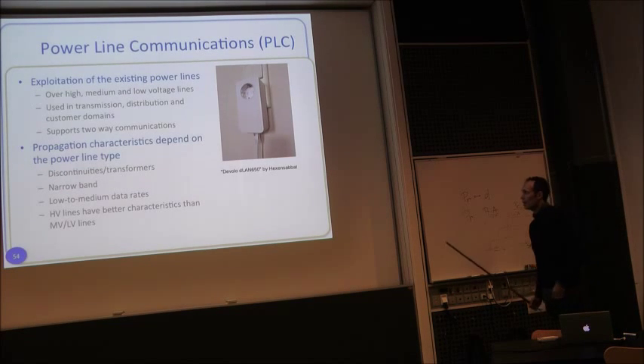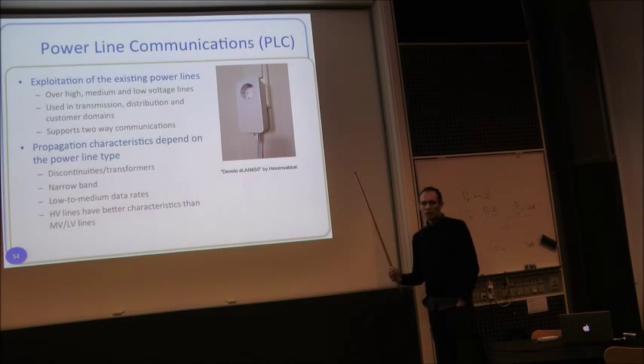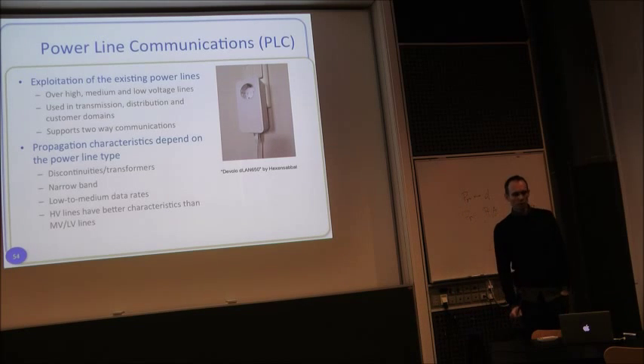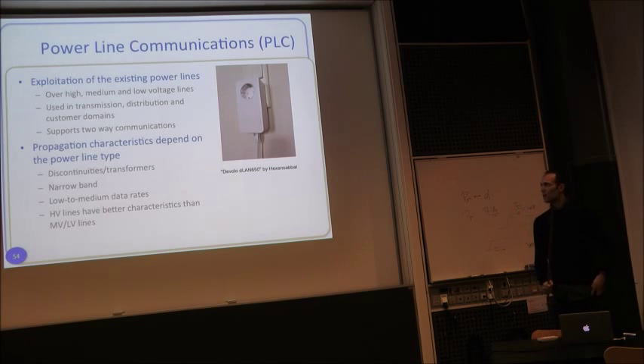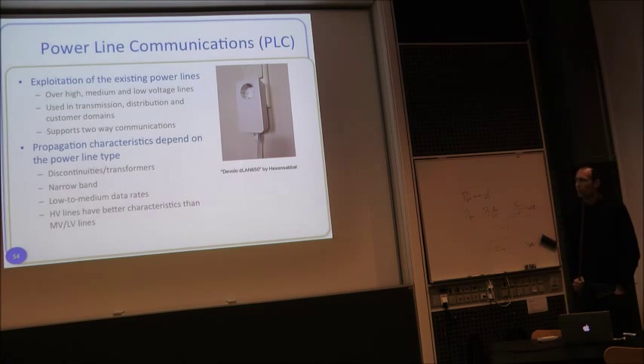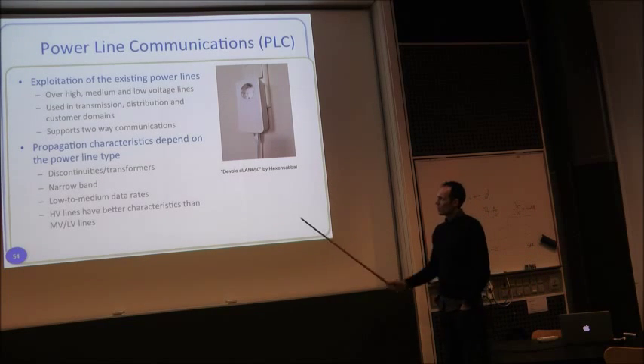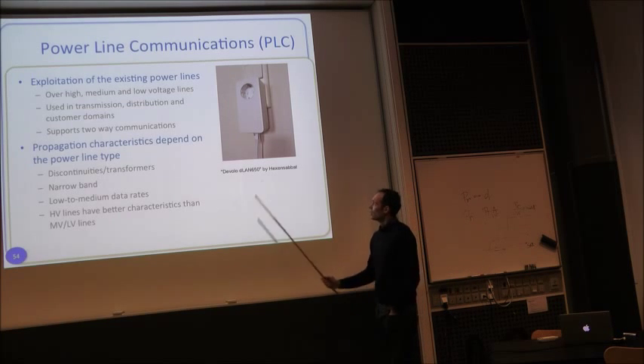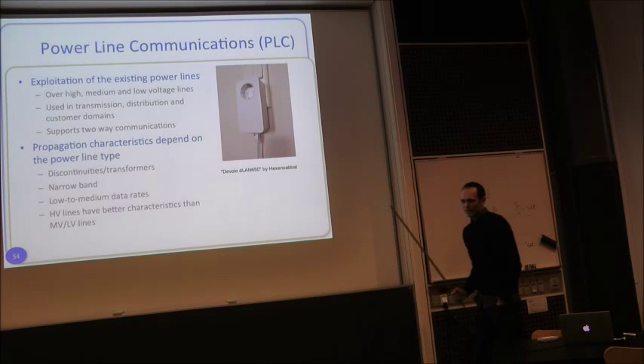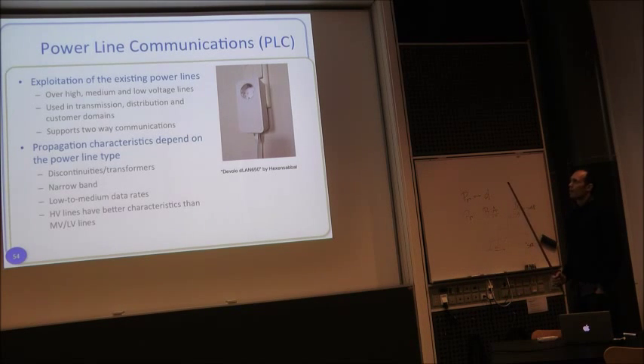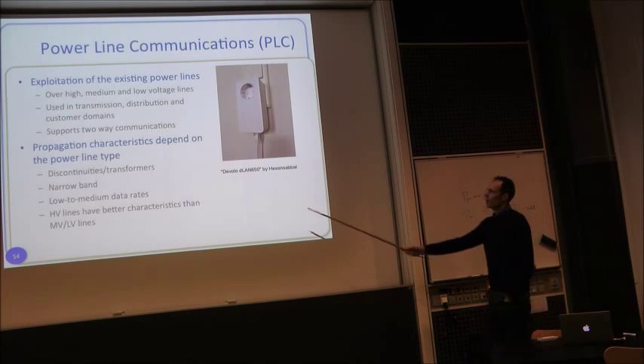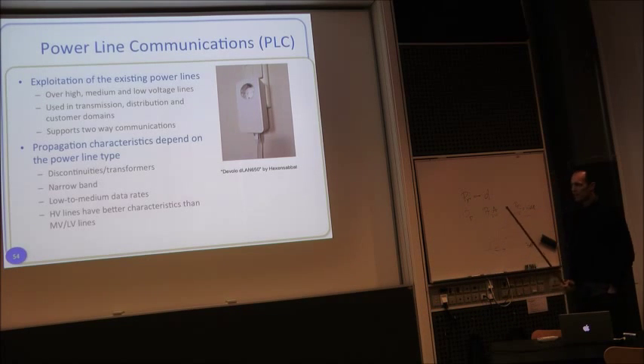Power line communications: the idea is powerful, using existing power lines to transmit communication information, just upgrading the endpoints with communication modems. So it can be used in all segments of the grid. The problem is that it suffers from discontinuities and sources of impairment within the grid, so it's typically narrowband communication achieving low to medium data rates. As soon as you reach a transformer or other discontinuity, you have to bypass that point using some other communication technology.